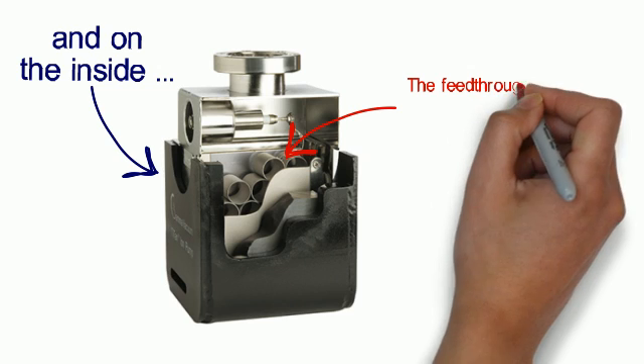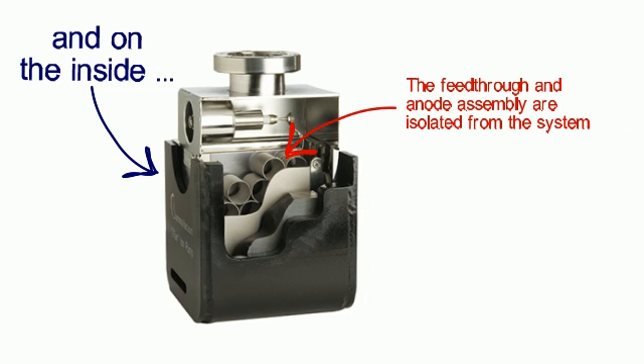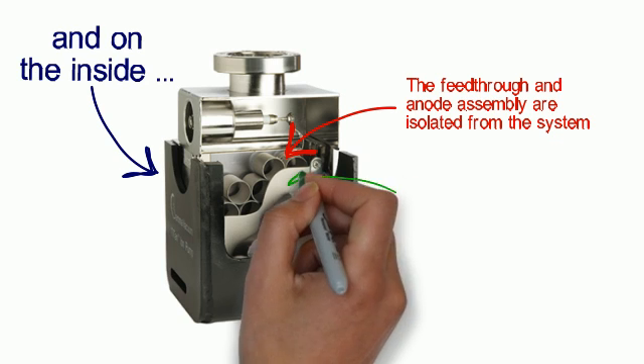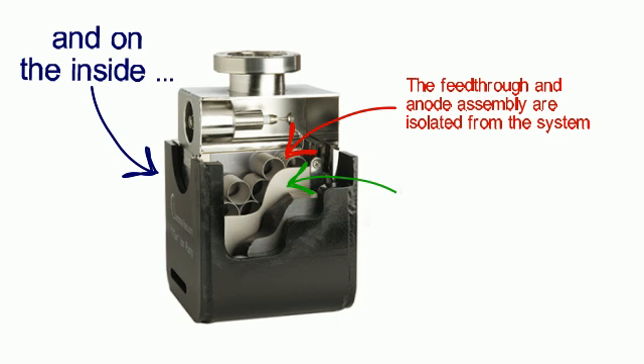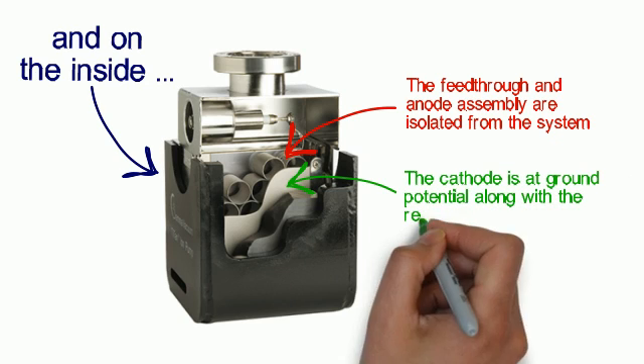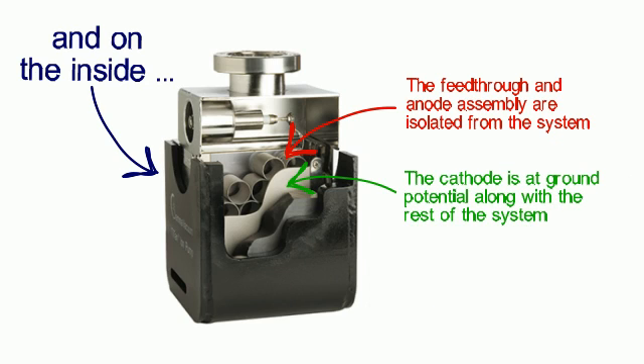We start with a feed-through and an anode assembly made out of stainless steel anode tubes. Those are isolated from the rest of the system, electrically isolated that is. Pointing to the green there are cathodes that are at ground potential along with the rest of the system.